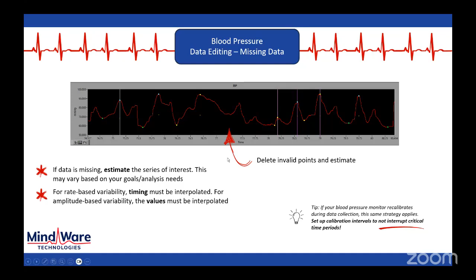And so this is great and it's important to do, but you don't want this to happen in the middle of your critical tasks. You want to make sure that you preserve that information. So there are ways in most instruments to set up calibration intervals so that you know that it's not going to occur when it's most important to you to collect this data. You can also disable it altogether. I hesitate to recommend that because you do need to recalibrate them. If you're measuring continuous blood pressure for an hour, you better have a calibration in there somewhere, or else you're going to notice as you're analyzing your data over time, it becomes less and less accurate. But you can time these intelligently. You can plan for downtime in your protocol to allow for this recalibration to occur so that you get the best of both worlds. You get all the critical data when you absolutely need it. And you get the accuracy that comes along with these calibrations within the protocol. If you need any help with that, reach out to our support team. We can always assist.